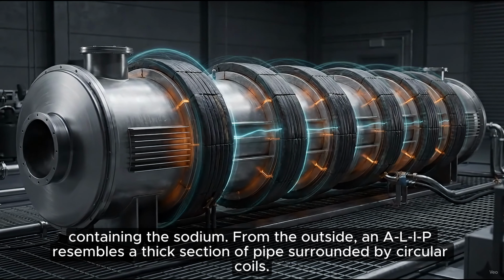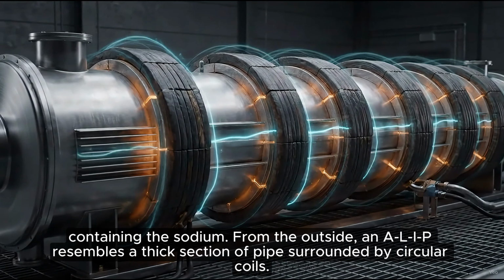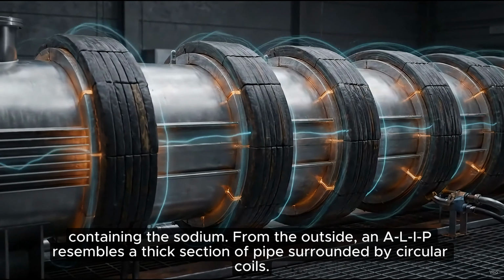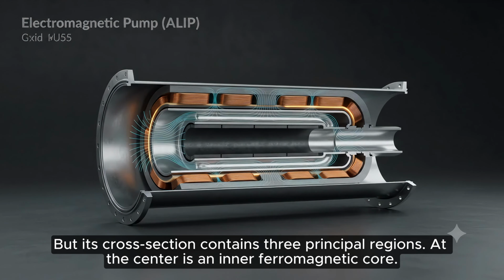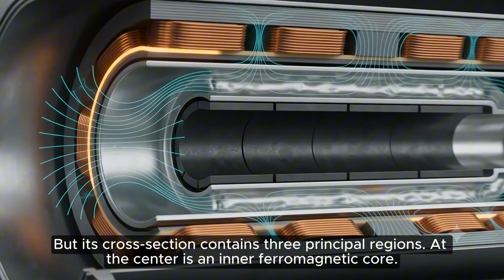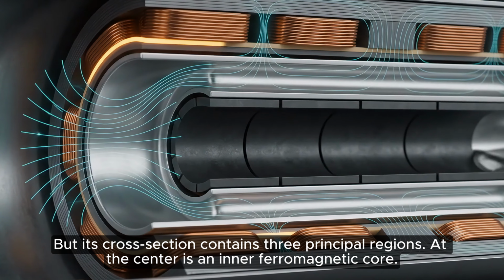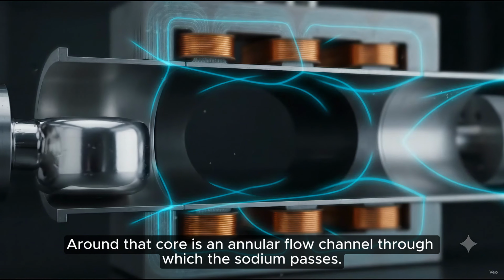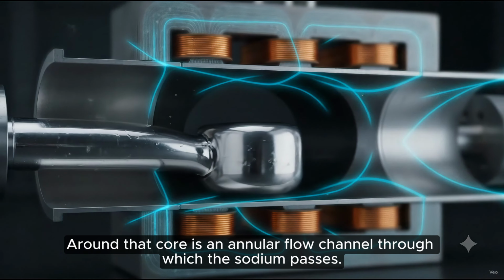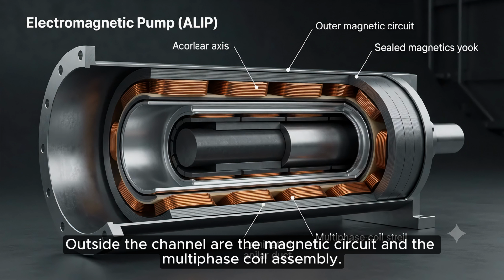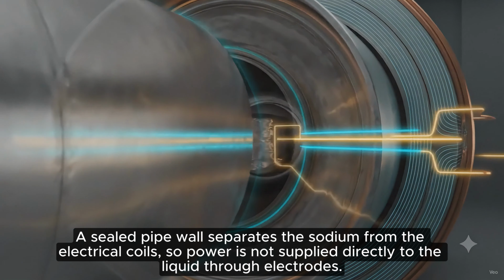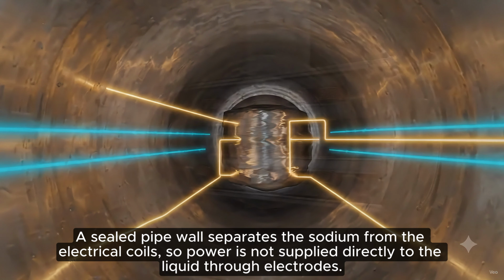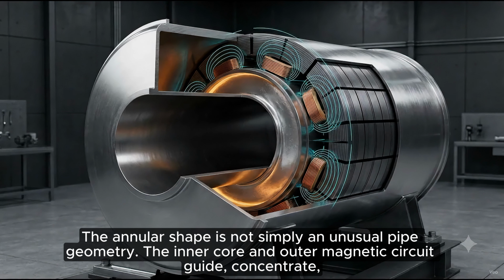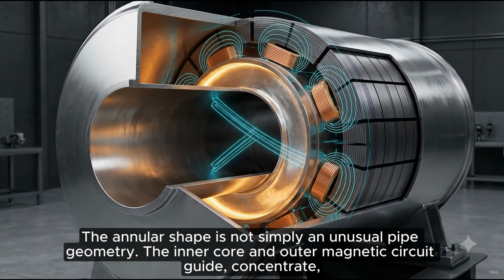From the outside, an ALIP resembles a thick section of pipe surrounded by circular coils. But its cross-section contains three principal regions. At the center is an inner ferromagnetic core. Around that core is an annular flow channel through which the sodium passes. Outside the channel are the magnetic circuit and the multiphase coil assembly. A sealed pipe wall separates the sodium from the electrical coils, so power is not supplied directly to the liquid through electrodes. The annular shape is not simply an unusual pipe geometry.